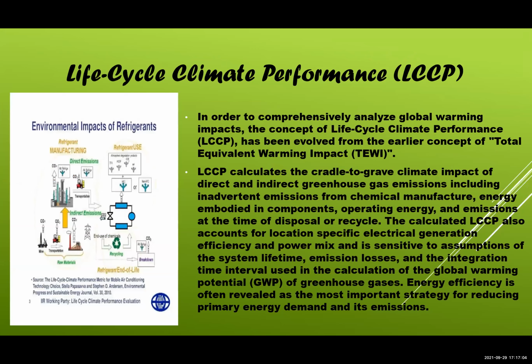And Omar briefly mentioned life cycle climate performance. This is a tool which we have been using in the past, but not many people took it seriously, because it started with TEWI, total equivalent warming impact, and then it was broadened and refined to be called life cycle climate performance of refrigerant systems. LCCP encompasses the entire life cycle: production of the refrigerant, transportation of the refrigerant, and charging, installation, running, operation, then end of life. Therefore, it encompasses the entire life cycle of the unit, and you can calculate and compare the performance of a refrigerant in a system using LCCP analysis.